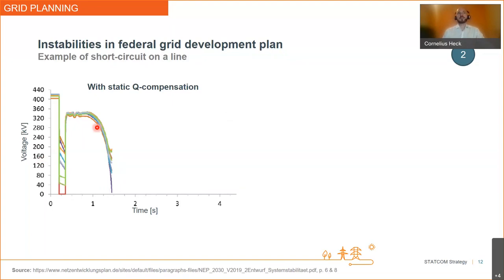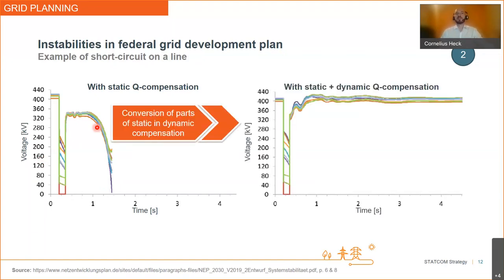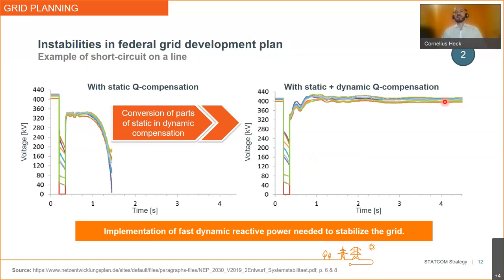So there's no stable operation possible here, but it could be stable if you just converted parts of this static compensation to dynamic compensation, which we did here. And here we just took the number that we calculated earlier, so the 9 gigawatt of STATCOM for our control area. And as you can see, now we have some really smooth voltage recovery, and even already after about 3 to 4 seconds, we'll have perfect conditions once again. So for now, we have answered the question that we need to implement fast dynamic reactive power in order to stabilize our grid.